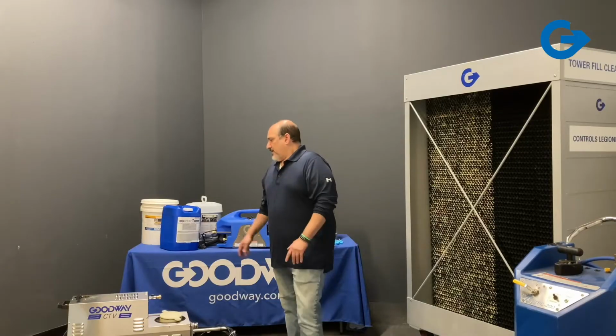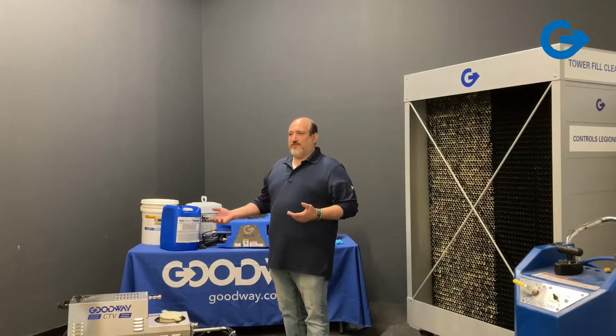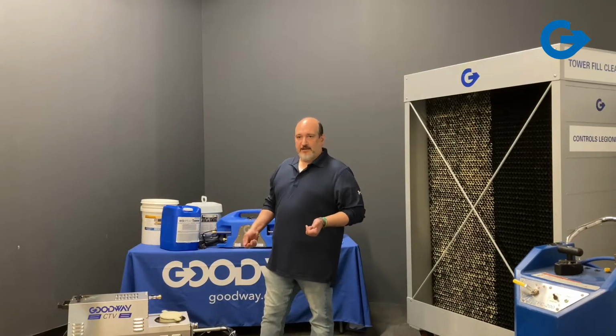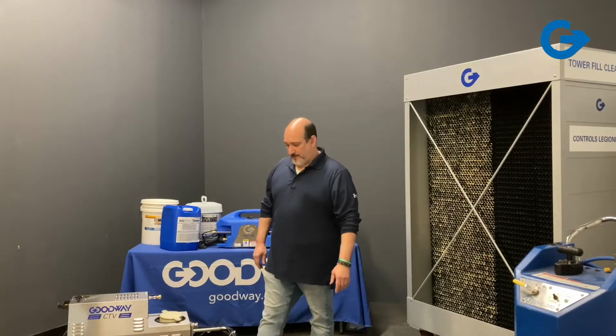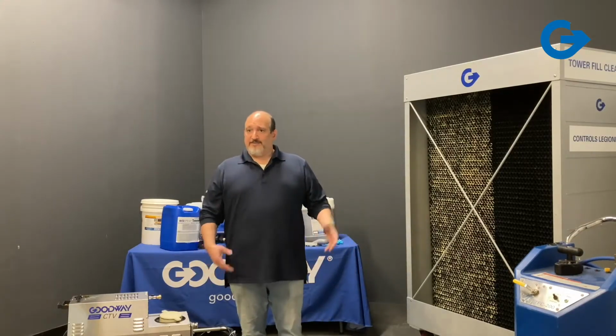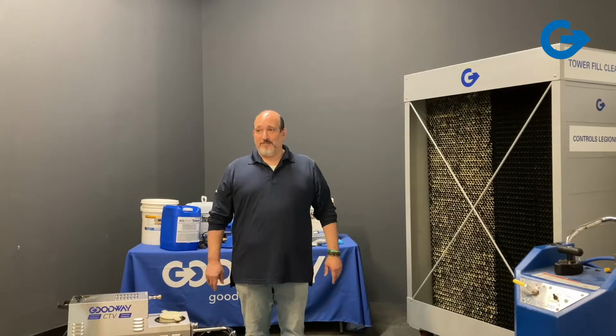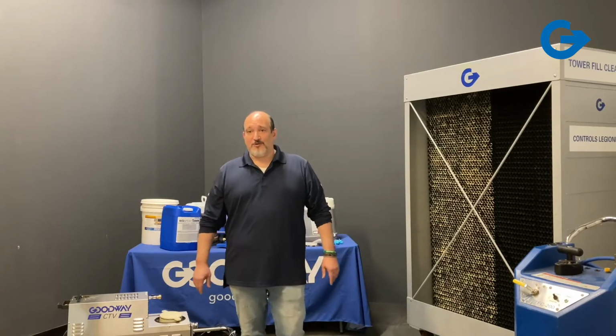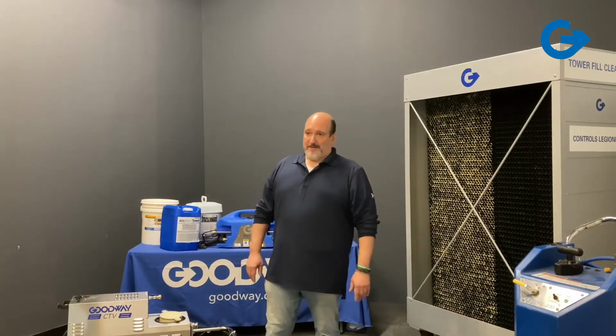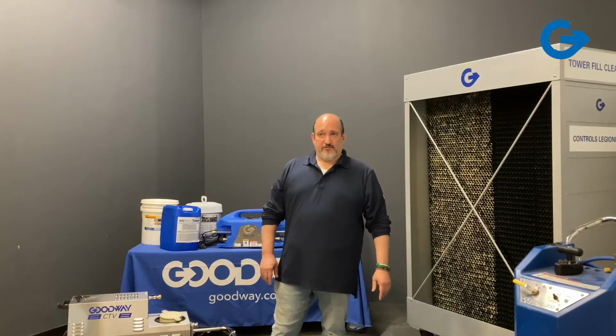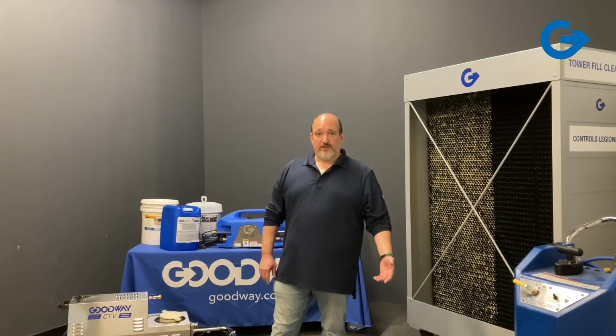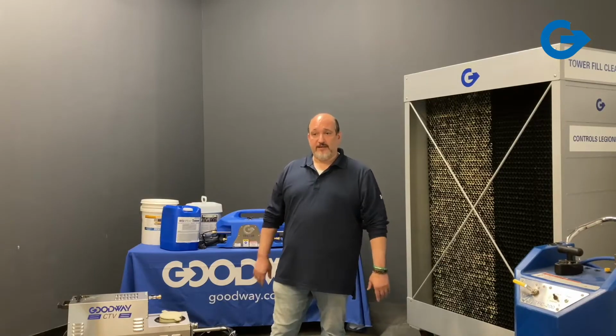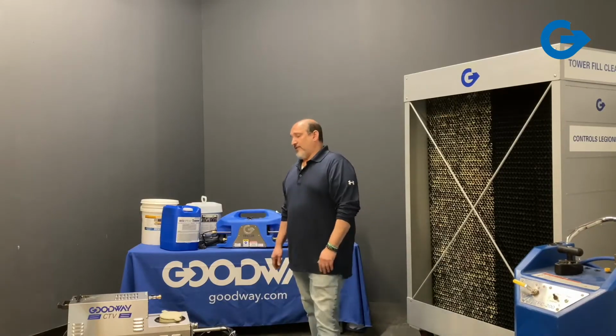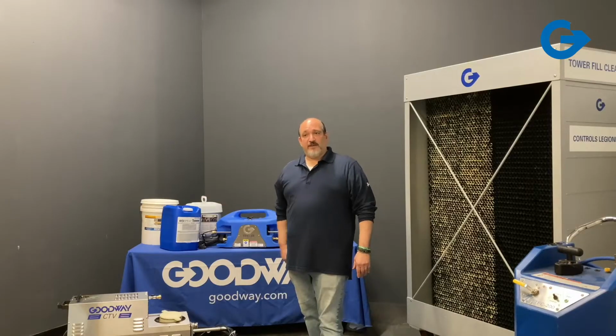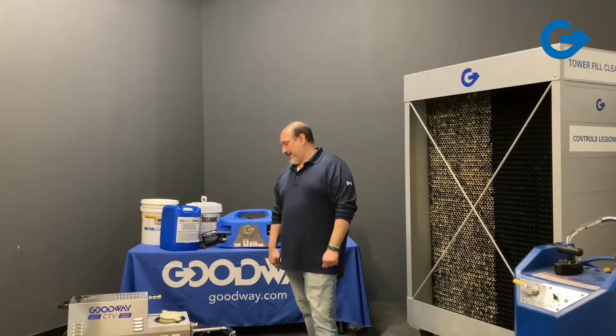So sometimes the 5 or 10% of water that you might go through when you're vacuuming is too much for some places. In Las Vegas, the water is very valuable, maybe even more so than the chemical that's used to treat it. California's got some pretty strict restrictions on how much water you can use, or how much water they're actually trying to save now in the heating and cooling process. So they don't want to lose that 5 or 10% of the water while they're vacuuming.